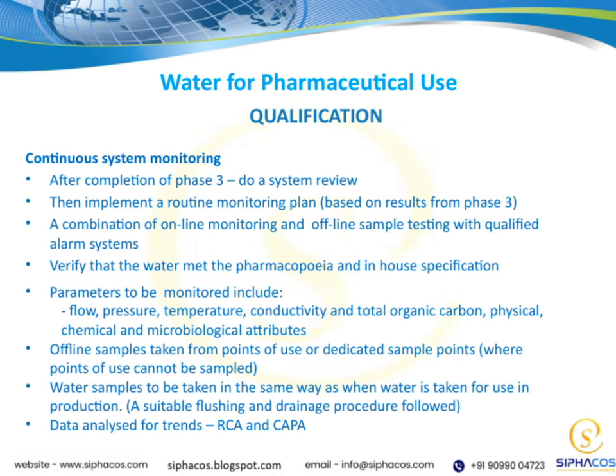After completing Phase 3 of our validation, a thorough system review is essential to evaluate performance and identify any improvements needed. Based on the results from Phase 3, we then establish a routine monitoring plan, which combines online monitoring with offline sample testing, supported by qualified alarm systems to alert us immediately if parameters go out of range.